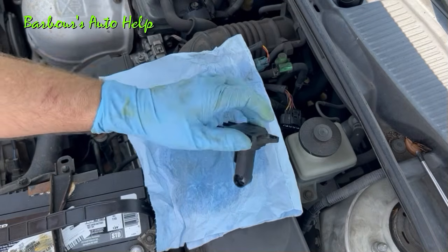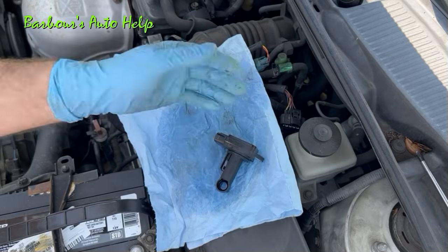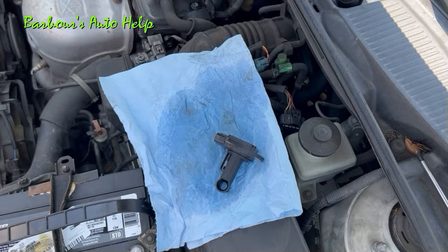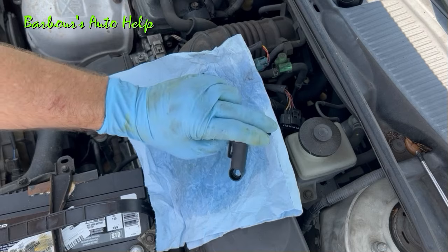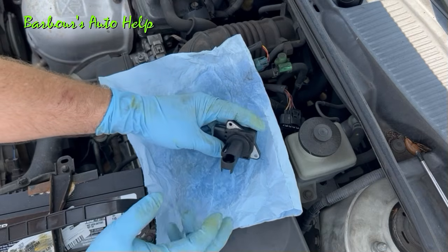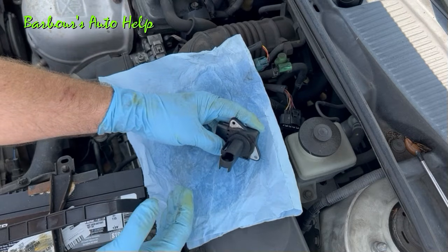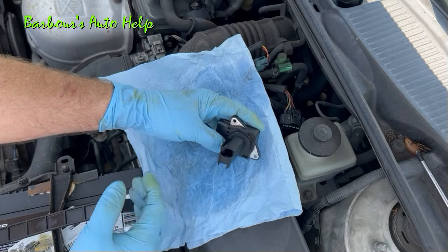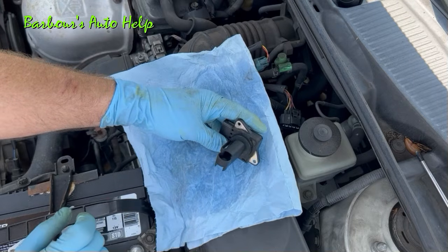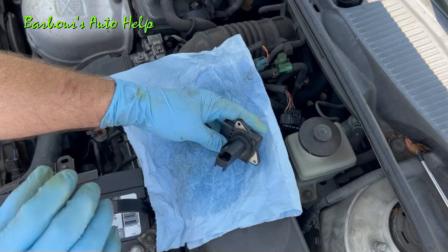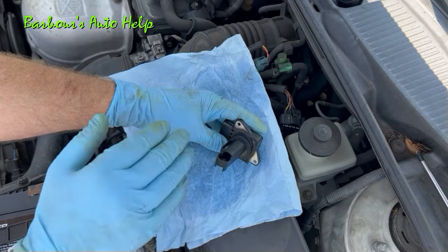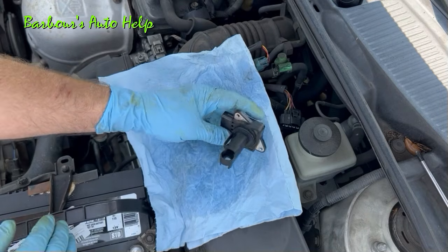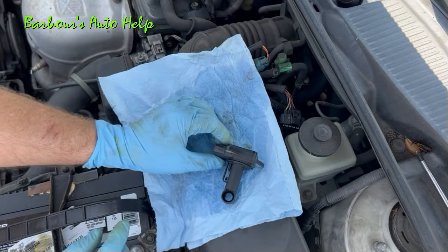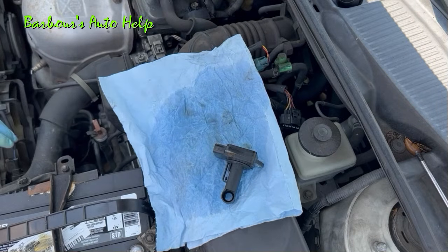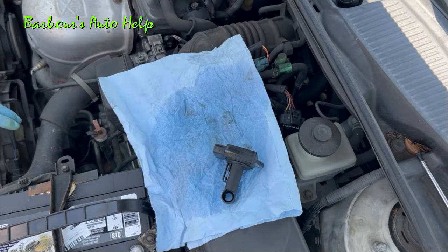What you want to do is set the sensor down and let it dry for about 15 minutes or so. If you want to make sure it's good and dry, you can take some canned air, like the kind used for cleaning circuit boards and keyboards, and gently spray it down in there. You don't want to spray compressed air down in there too forcibly because you don't want to damage the hot wires. Spraying it and letting it dry a good long time gives you added insurance that it's totally dry before you put it back in.